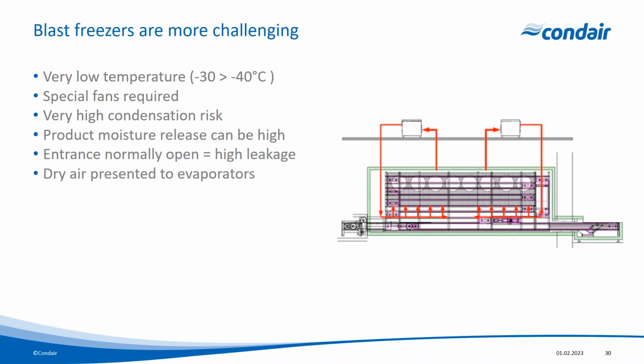Blast freezers are more challenging. With a blast freezer, we've got low temperatures, -30 to -40, in very high air volumes, as we've got product either going through a spiral blast chiller or a conveyor blast chiller, and we're reducing the temperature of that product very, very quickly with high air volume. Now, when we get down to these lower temperature conditions, you've got to have specialized fans within the dehumidifier to make sure that the grease in the motors will not freeze up. And there's a very high condensation risk with a blast freezer. We've got an open-ended process here. So you've got moisture that's going to come in. And so our moisture leakage is going to be very high.